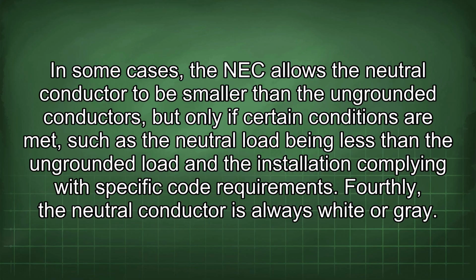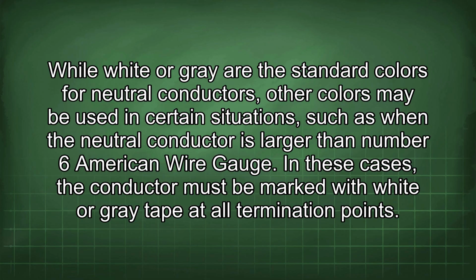code requirements. Fourthly, the neutral conductor is always white or grey. While white or grey are the standard colors for neutral conductors, other colors may be used in certain situations, such as when the neutral conductor is larger than number 6 American wire gauge. In these cases, the conductor must be marked with white or grey tape at all termination points.